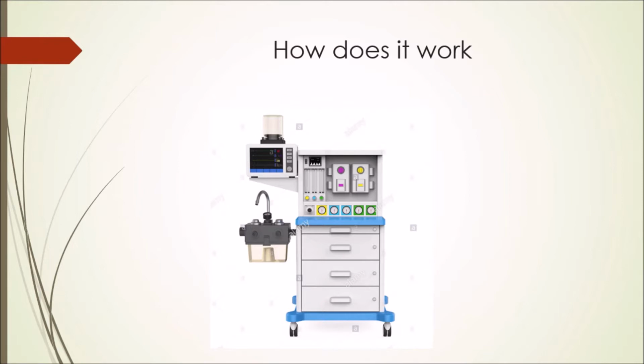The first one is gas supply, which creates and provides the gas mixture and patient breathing monitors. The second one is data analysis, which is hardware and software that collect and process all the information. Then the third one is physiological monitors, which indicate levels and variation of physiological variables associated with cardiopulmonary function. If we continue, let me show you the parts of a basic anesthesia machine.